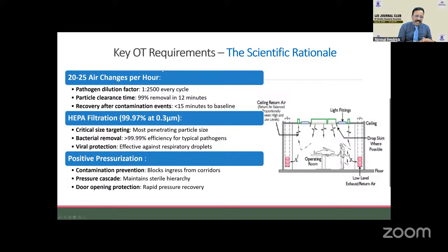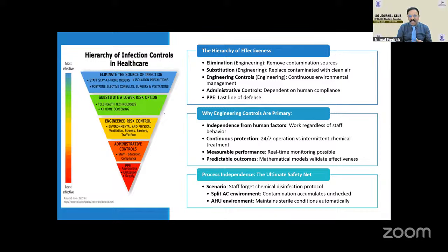And this has a scientific rationale because of the particle clearance time, 99% removal in 12 minutes, and HEPA filtration, where the most penetrating particle size are filtered by the HEPA, and positive pressurization really helps in blocking the ingress from the corridors, maintains sterile hierarchy, and rapid pressure recovery. I already told you about the hierarchy of effectiveness. Elimination is very important: removing the contamination sources by clean air, replacing it with the clean air, and the continuous environmental management of fresh air coming into the system is important.